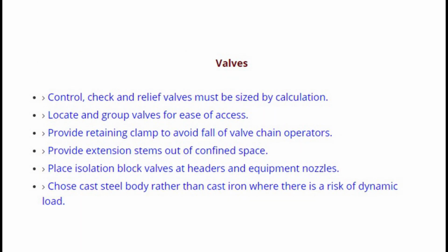Good practice for valves. Number 1. Control, check and relief valves must be sized by calculation. Number 2. Locate and group valves for ease of access. Number 3. Provide retaining clamp to avoid fall of the valve chain operators. Number 4. Provide extension stems out of confined space.